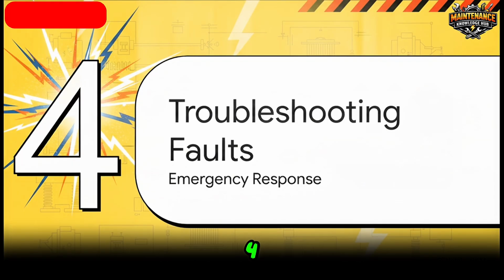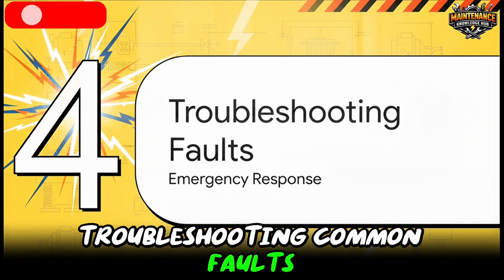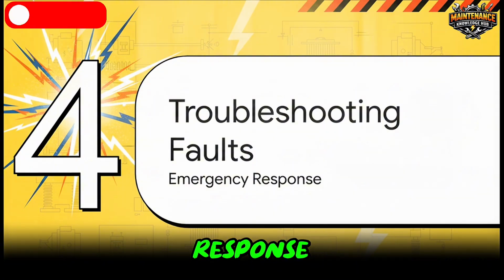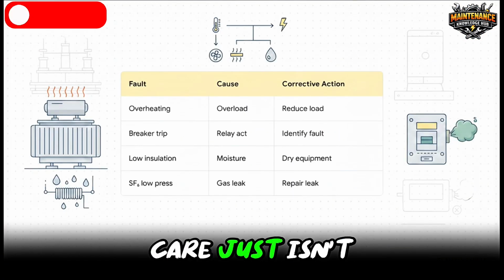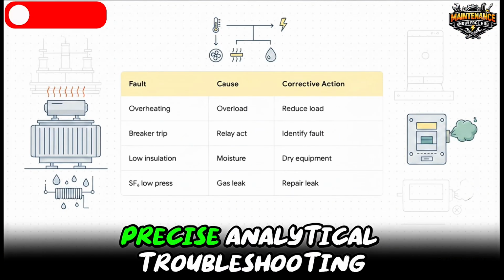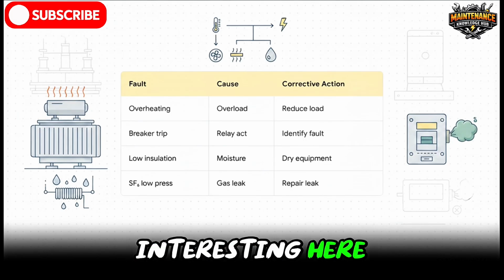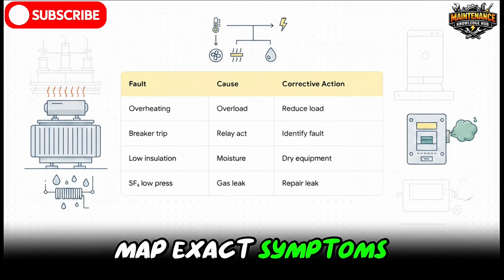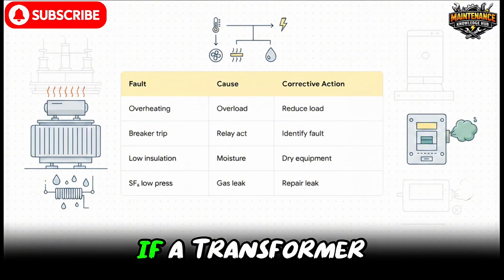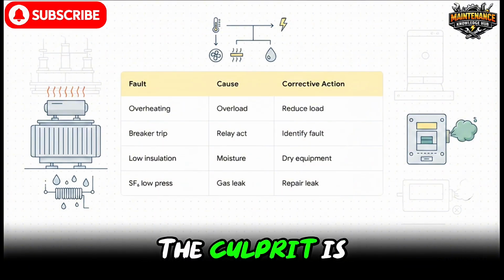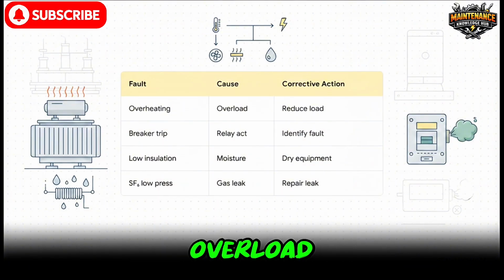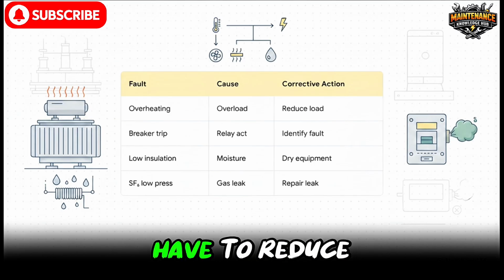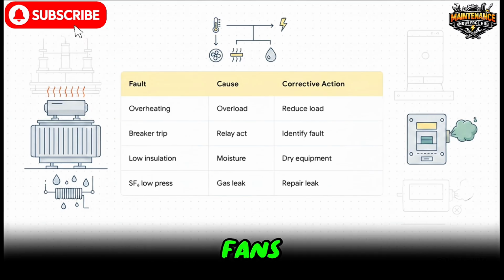All right, Section 4, Troubleshooting Common Faults. Let's talk emergency response. So, when preventive care just isn't enough, we rely on precise, analytical troubleshooting. Now, what's really interesting here is how we map exact symptoms to direct actions. If a transformer is overheating, the culprit is almost always an overload or a cooling failure, which means you have to reduce the load and inspect the fans.